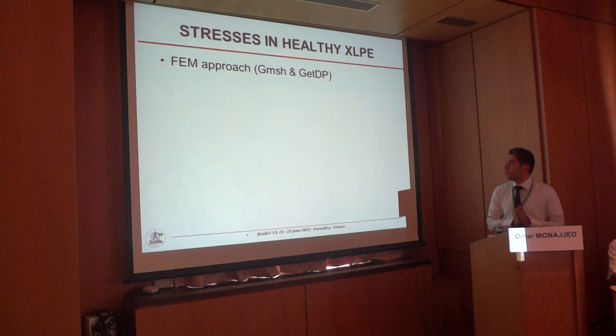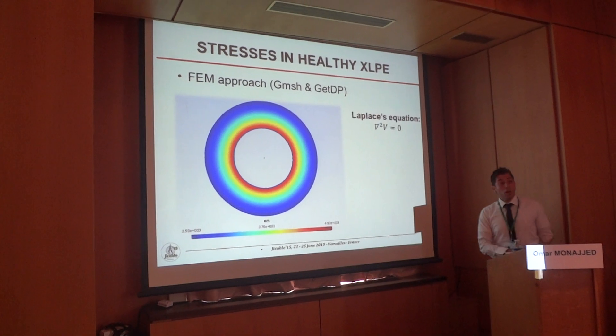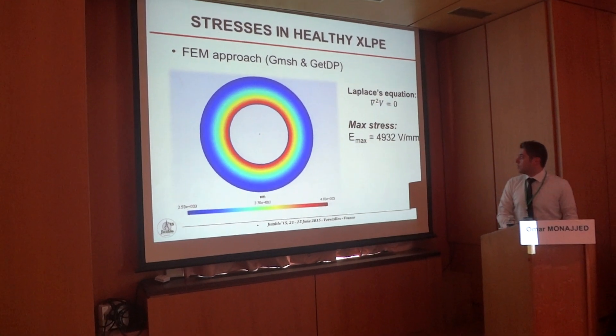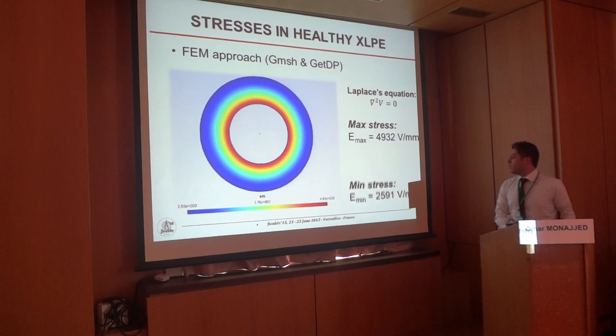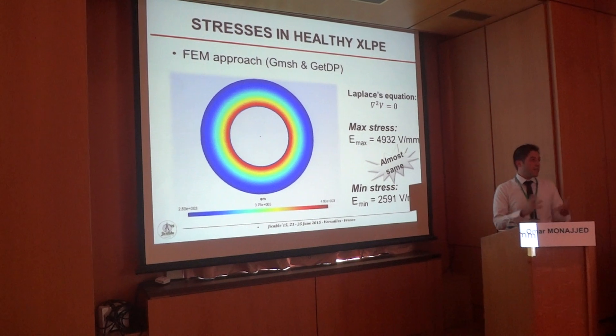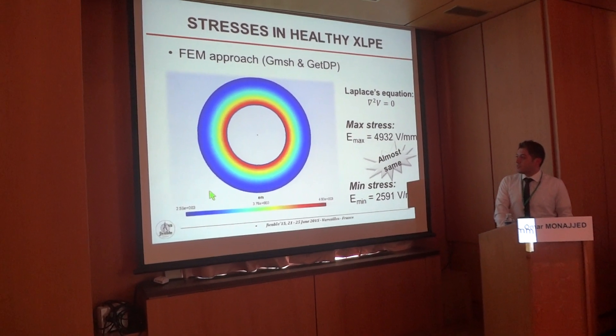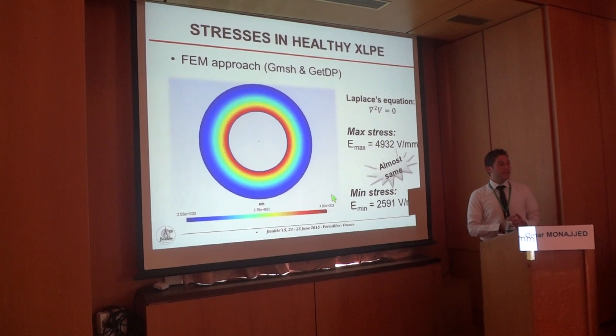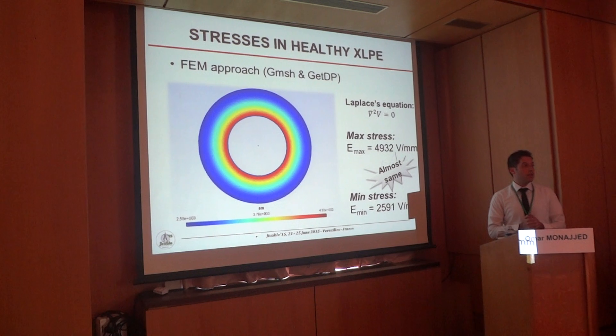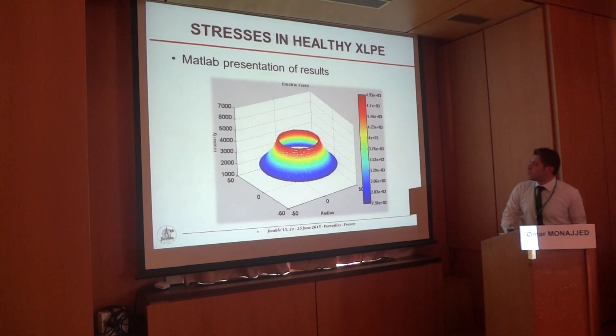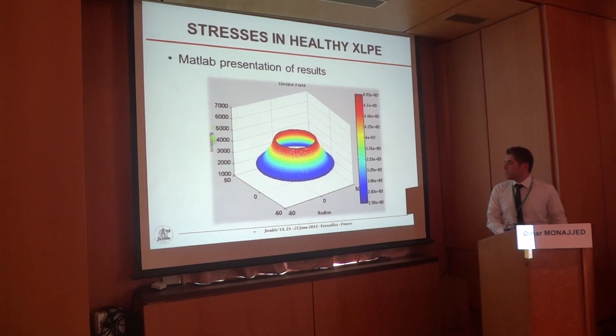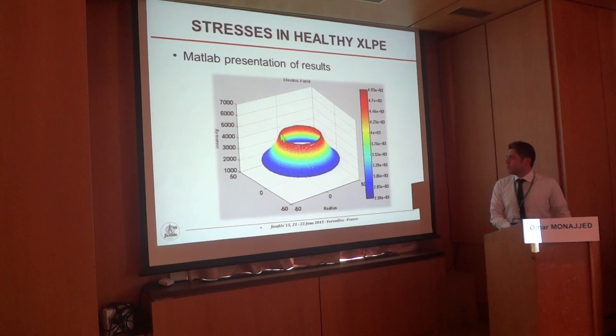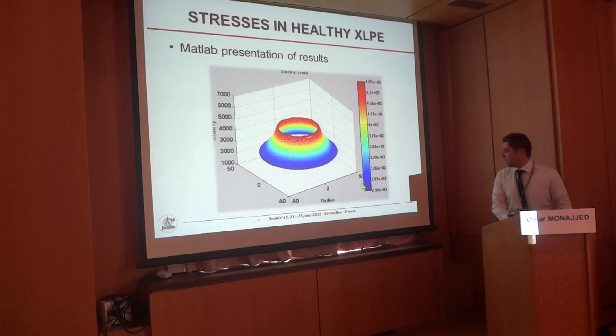We now move to the FEM approach using Gmsh and GetDP, where we solve Laplace's equation: ∇²φ = 0. After solving it, we get a maximum stress of 4932 V/mm and a minimum stress of 2591 V/mm, which is almost the same as the mathematical approach. This figure shows the results — stress ranges from 2.5 kV/mm up to 4.9 kV/mm. To better understand this result, we present it in MATLAB in 3D. We can see the maximum stress on the inner semi-con of 4.9 kV/mm, and that stress decreases to reach its minimum at the outer semi-con of 2.5 kV/mm.